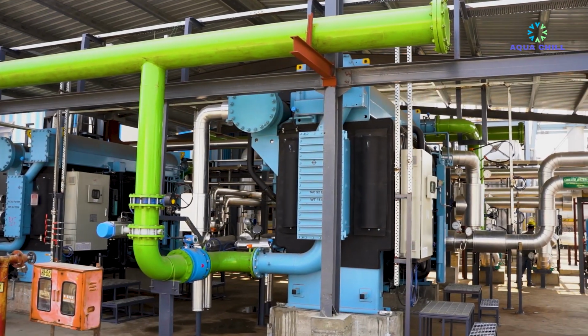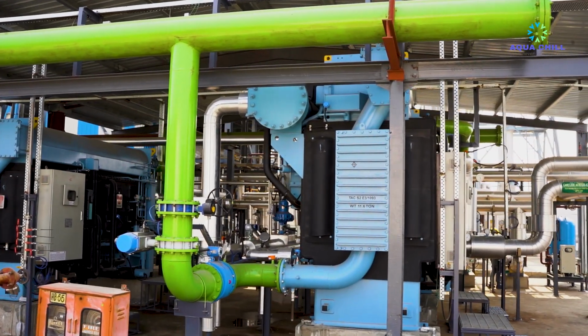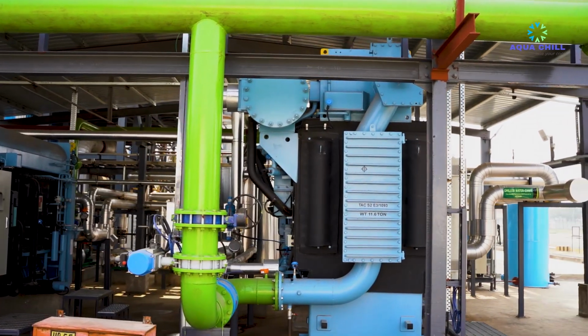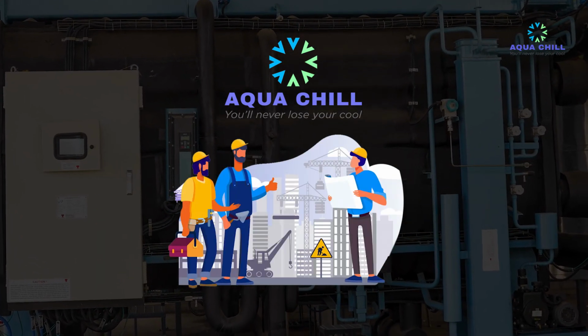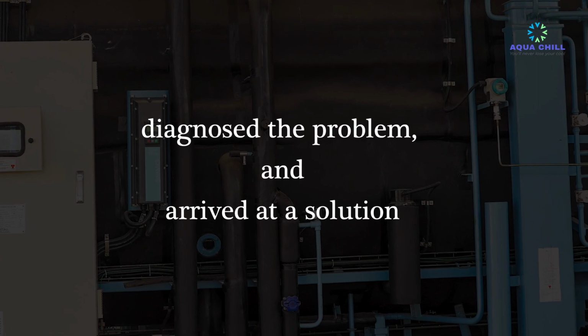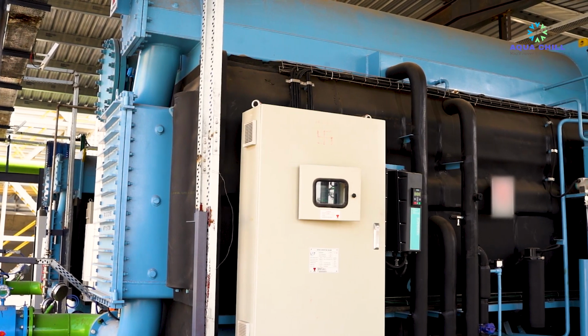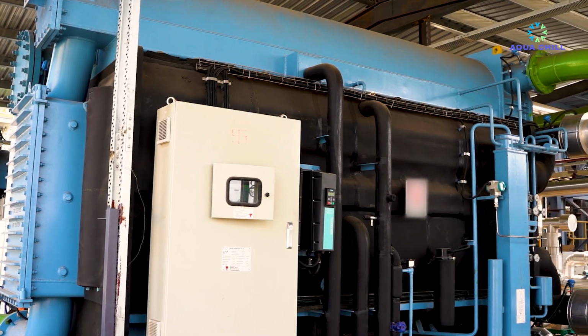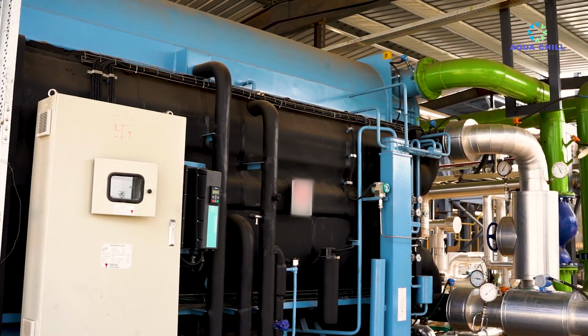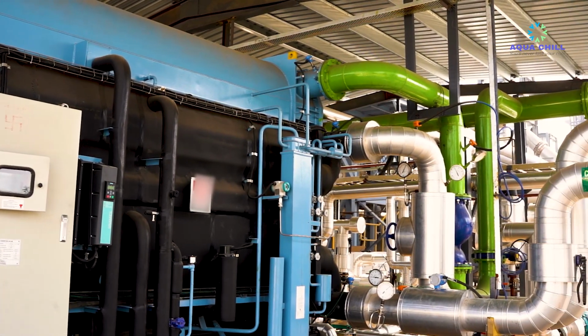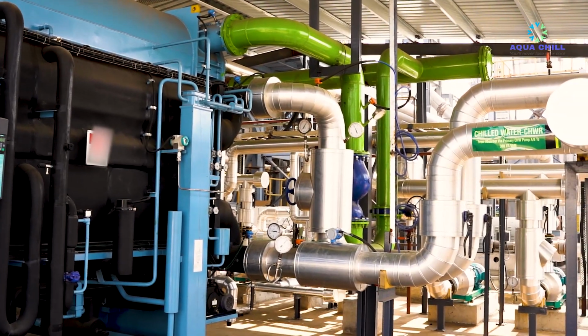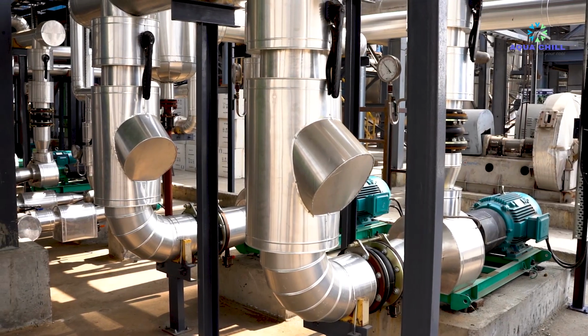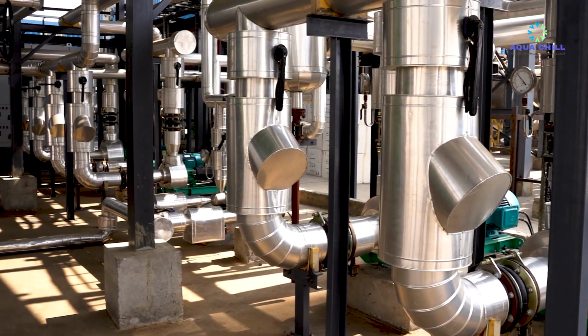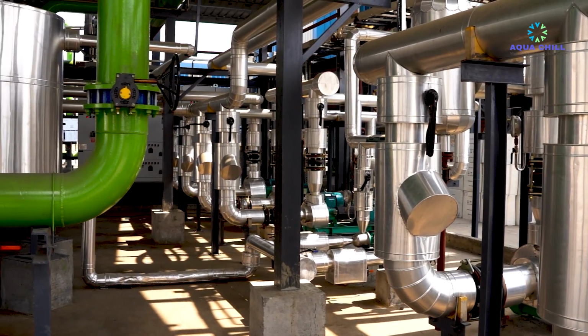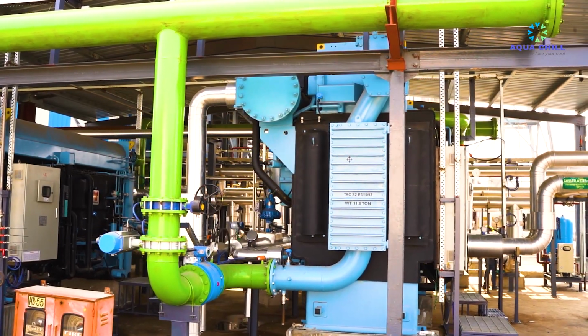Hence, the mass of air that is fed to the synthesis process is the key parameter to achieve the rated output. Aqua Chill, along with the user team, deliberated, diagnosed the problem, and arrived at a solution. It was inferred that the suction air to the compressor needs to be cooled without impacting other process parameters so that the compressor can push the required mass of air to the synthesis process. Aqua Chill came up with a unique solution for improving the productivity of the process line by cooling the suction air of the process air compressor.